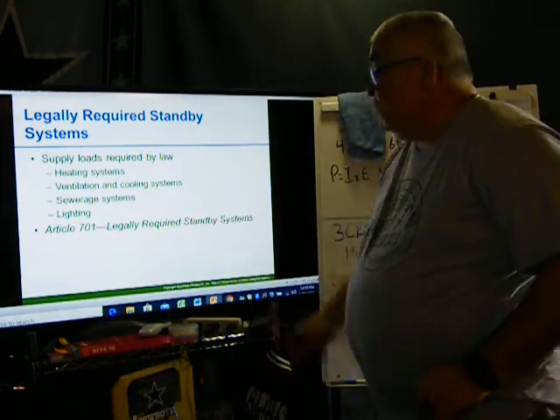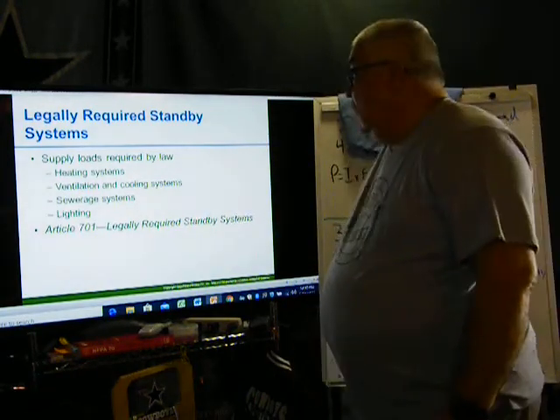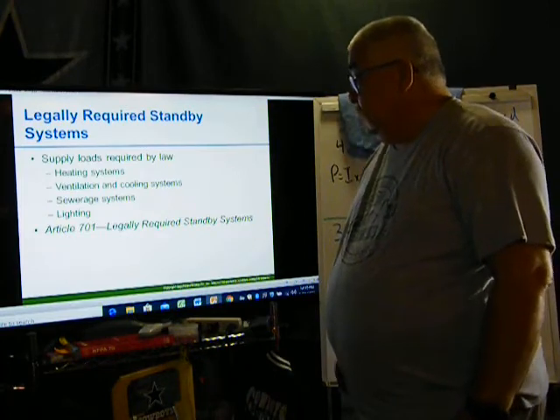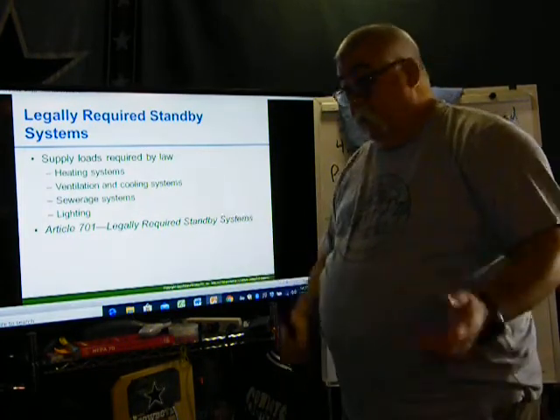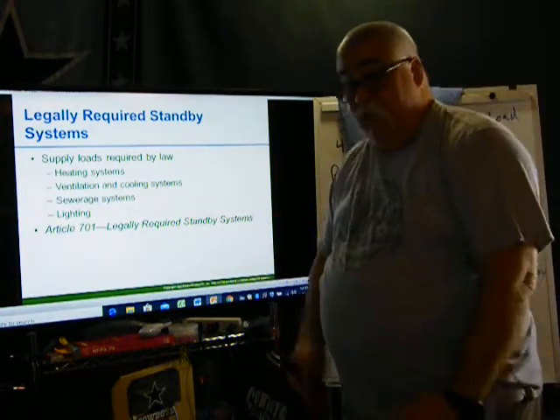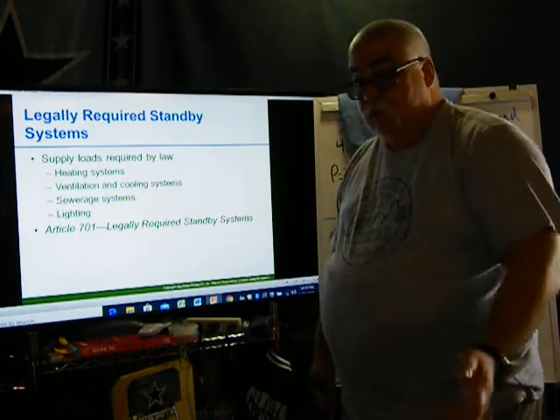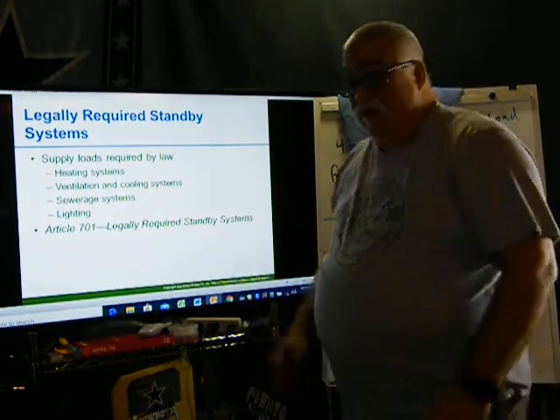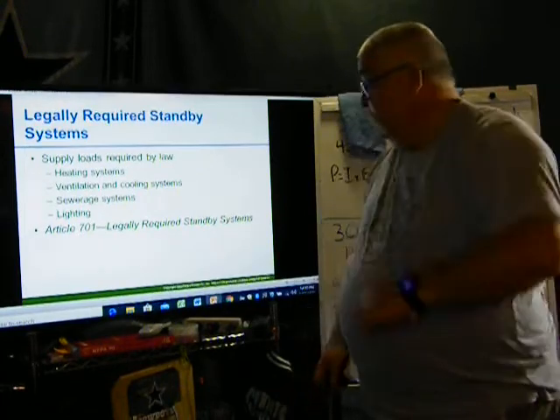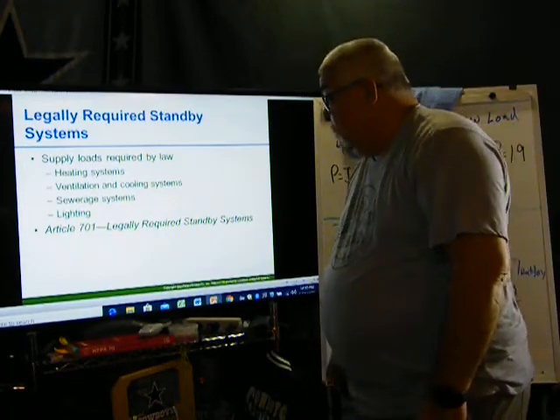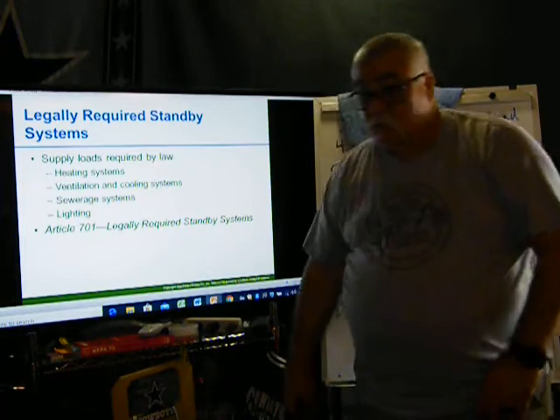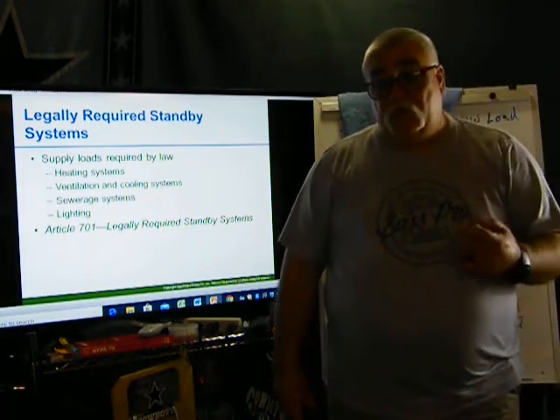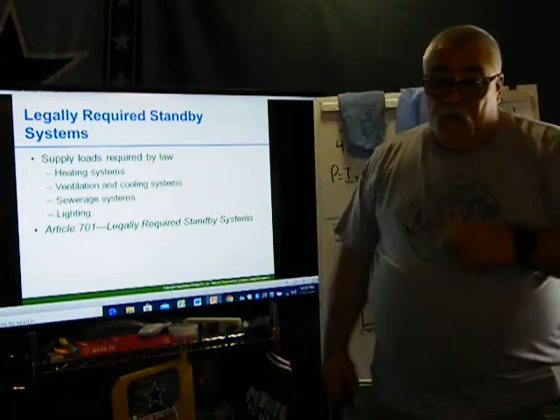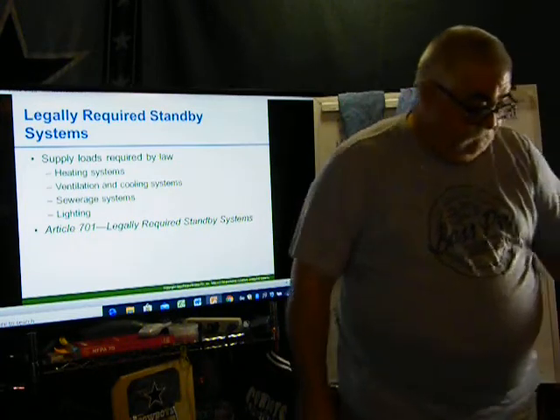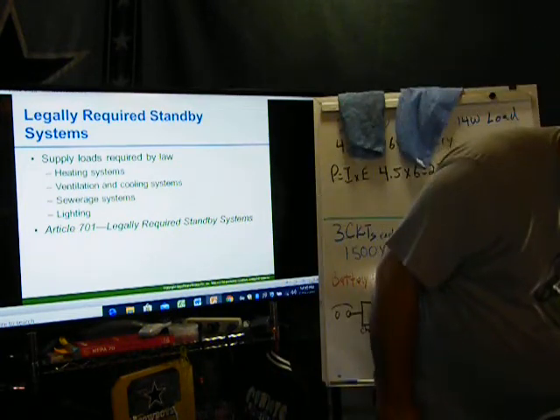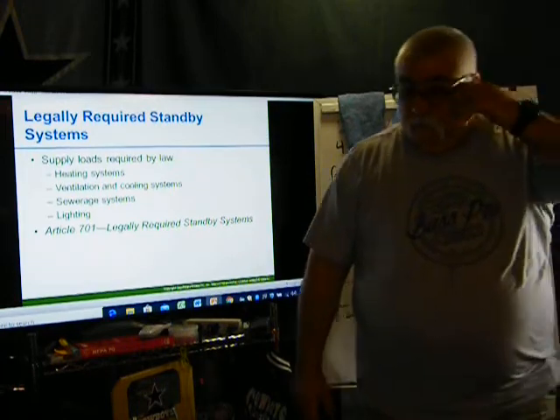So your heating systems, you got to keep the heating going. Ventilation and cooling. Sewer systems, if you got pumps, because it's going down to the basement, you got to come up 3 floors. Well, somebody goes to use this thing, it has to work. And lighting, so people can exit. And that is all in Article 701, legally required standby systems. Emergency power is Article 700. Legally required is 701. And the optional is 702.